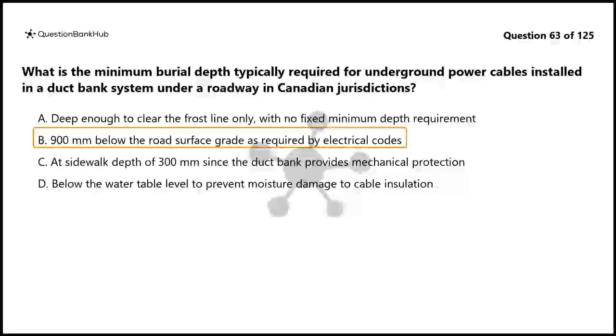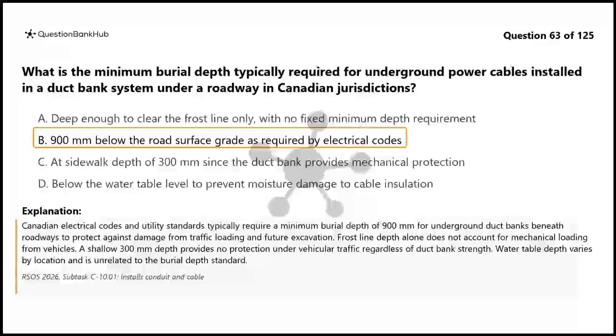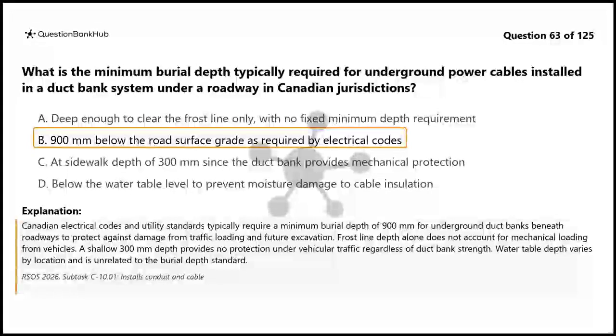The correct answer is B. Canadian electrical codes and utility standards typically require a minimum burial depth of 900 mm for underground duct banks beneath roadways to protect against damage from traffic loading and future excavation. Frost line depth alone does not account for mechanical loading from vehicles. A shallow 300 mm depth provides no protection under vehicular traffic regardless of duct bank strength. Water table depth varies by location and is unrelated to the burial depth standard.